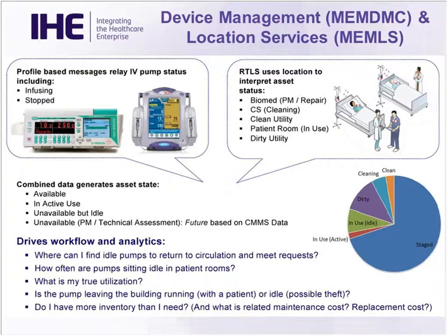But if you do have a piece of equipment that needs some assistance from clinical engineering, if you know where it is, then that improves your ability to just go in and service the equipment. So we have the medical equipment management location services profile. What this profile does is, and I love the word, abstracts the receiving system from the variety of technical approaches to identifying the location of objects. MEMLS focuses on how to identify the location of something in multiple ways.